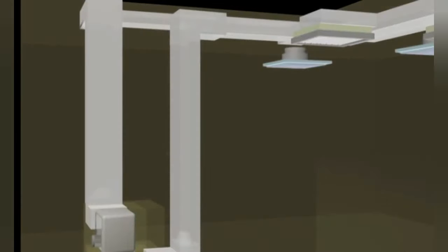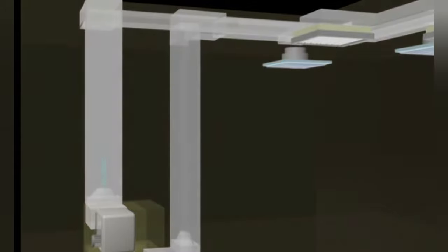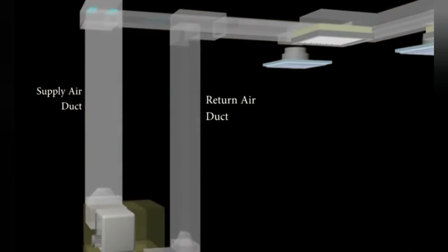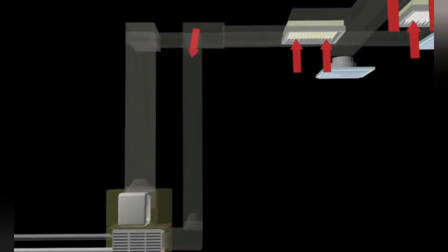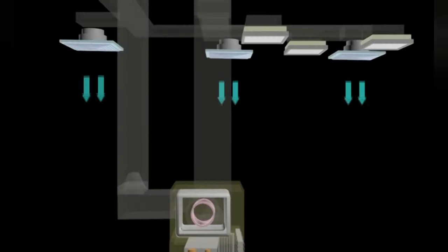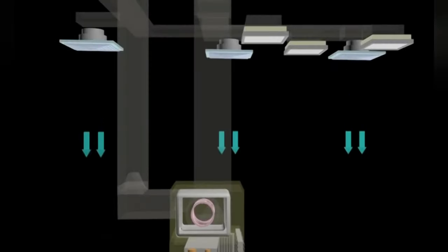The air flowing through a channel is called ducting. There are two types: supply air duct and return air duct. These ducts are coated with insulating material consisting of fiberglass wrapping with aluminum foil to reduce heat transfer from the environment. Air returning to the air handling unit passes through a filter before going through the cooling coil and returning to the room, ensuring the air is clean.